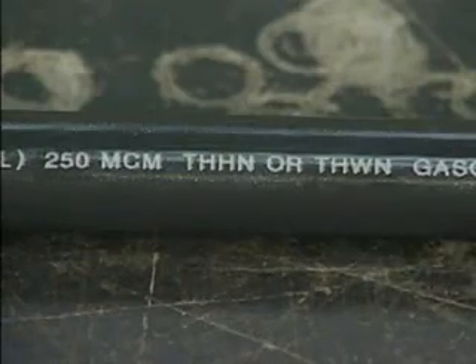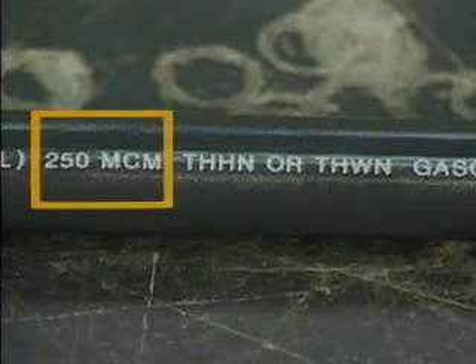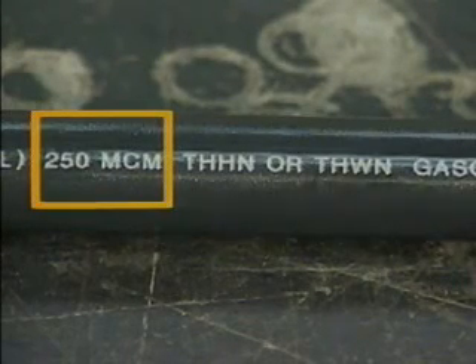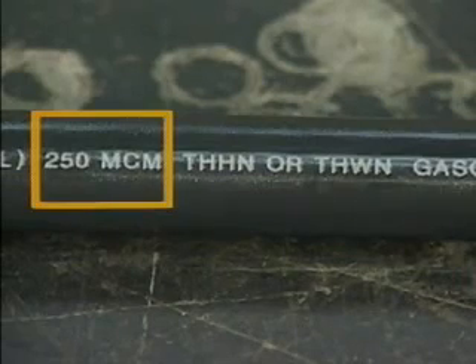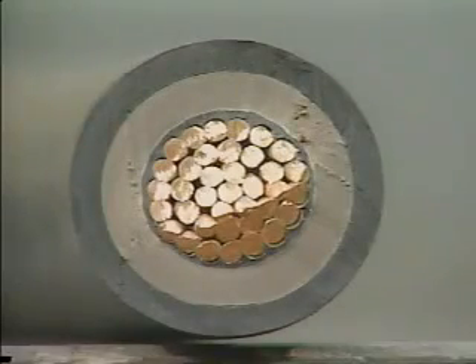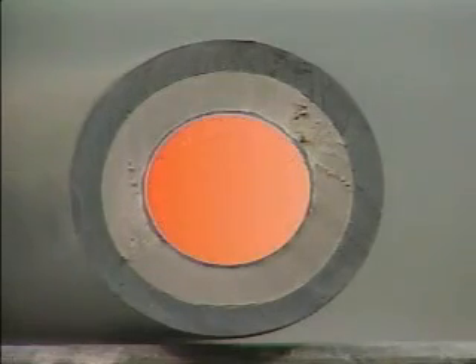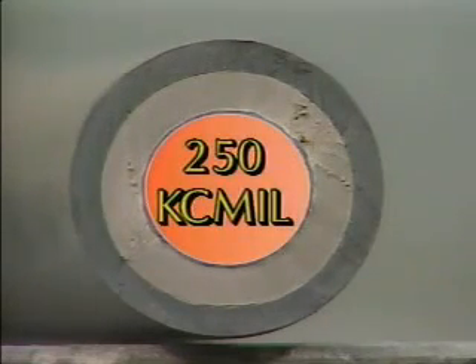You may also see circular mils abbreviated MCM. This conductor, marked 250 MCM, could just as accurately be labeled 250 kcmil. A 250,000 circular mill wire has an area equal to that of 250,000 circular mils. This system uses actual measurements, so the larger the number, the larger the wire.